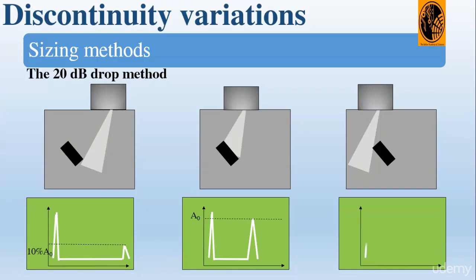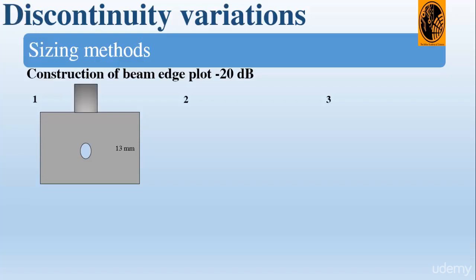Now let's see the beam construction at 20 dB. First step: find the hole at a depth of 13 mm with a zero degree probe, then maximize the signal by moving the probe until we get the highest signal from the hole. Turn the signal to full screen height using the gain function, then mark the position of the middle of the probe on the block.